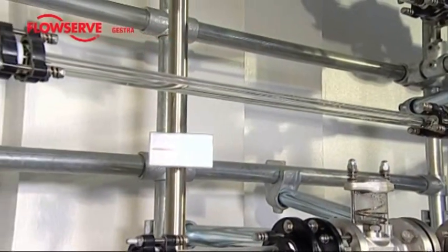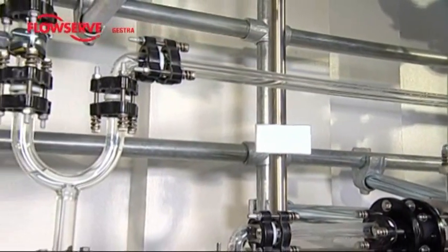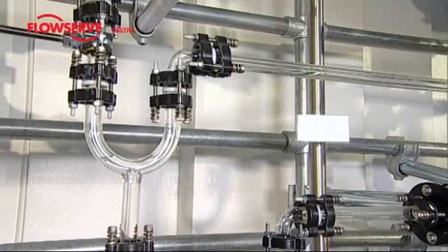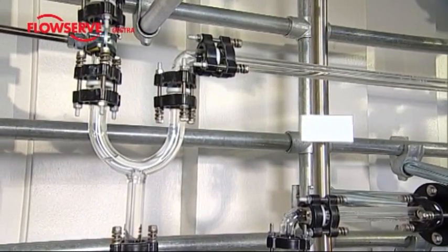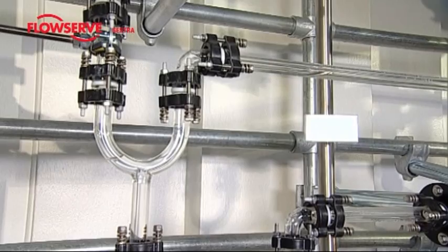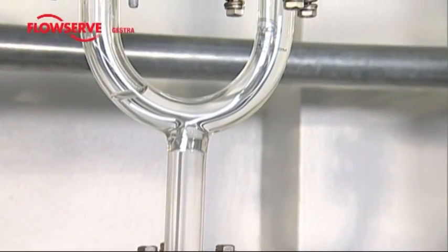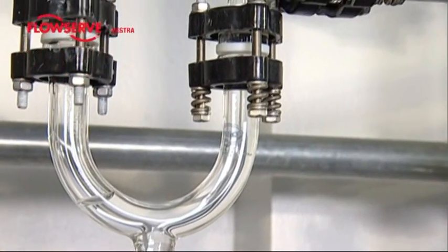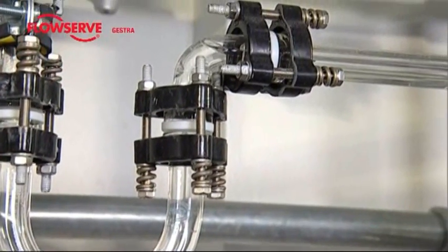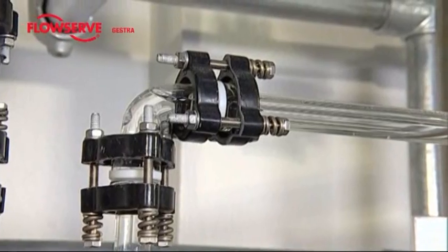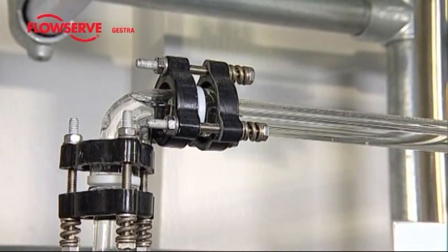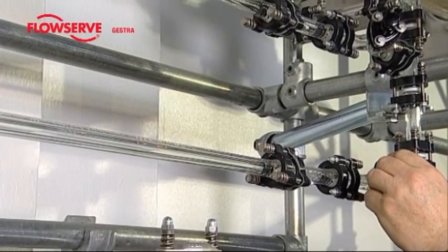This time, however, this part of the horizontal tube is arranged to have a slight drop towards a siphon. Having the siphon downstream ensures that there is always a steam bubble in the horizontal part, and the water flows along the bottom. Through their volume, the steam bubbles at the top of the tube form a buffer space, which minimizes the Waterhammer at startup and allows the startup process to be initiated faster and with less risk.